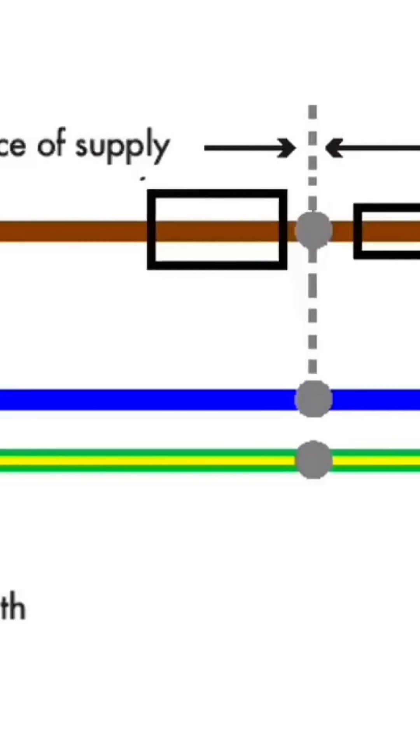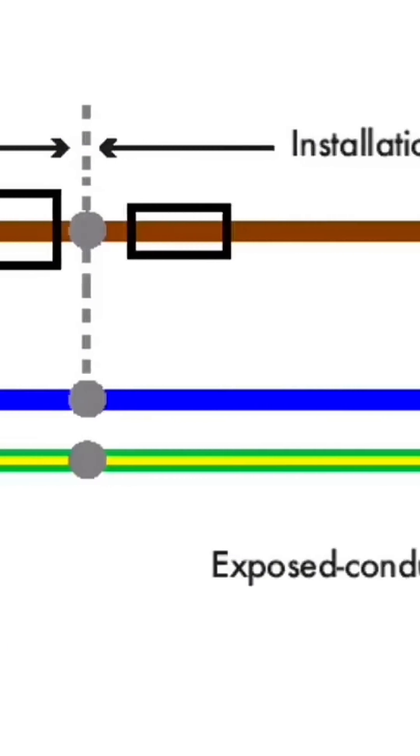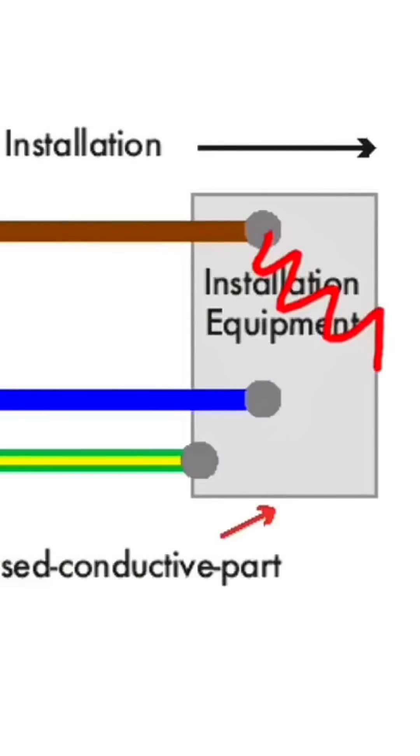The earth fault loop impedance path of an installation connected to a TNS earthing arrangement. In the event of there being a fault between the line conductor in the installation and an exposed conductive part, the fault path or earth fault path would be as follows.